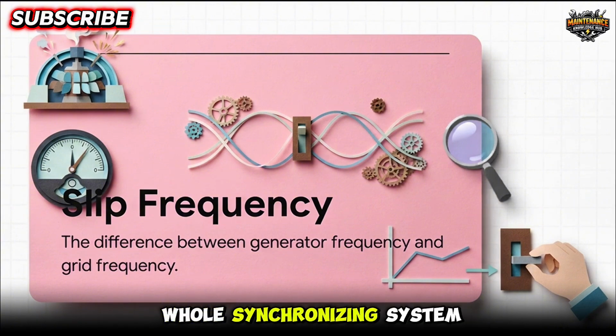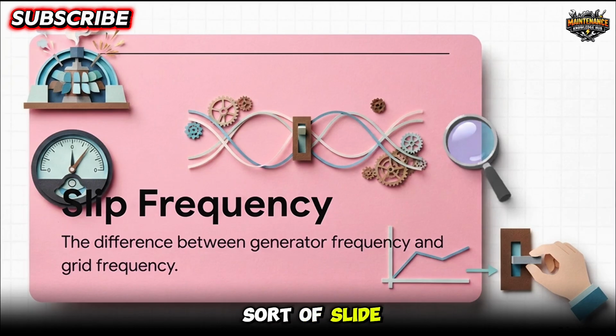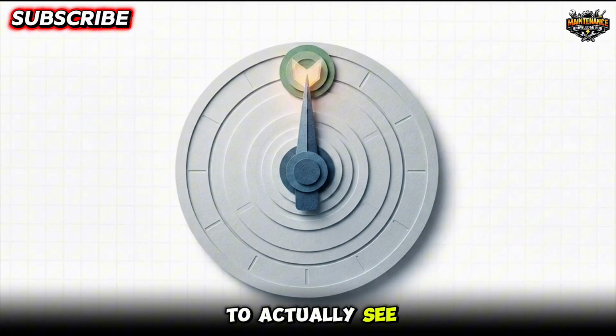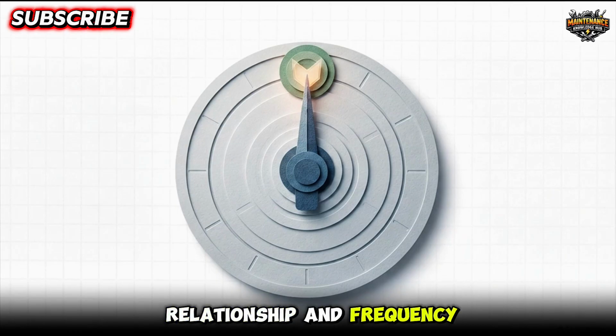It allows the whole synchronizing system to slowly slide into the perfect phase alignment, letting us predict the exact millisecond to safely close the breaker. To actually see this slip happening, operators use a super neat device called a Synchronoscope. Now, back in the day, older systems used synchronizing lamps that would physically blink bright and dark to show phase differences. But a Synchronoscope dial is way more precise. It gives you a visual read on the phase relationship and frequency difference.